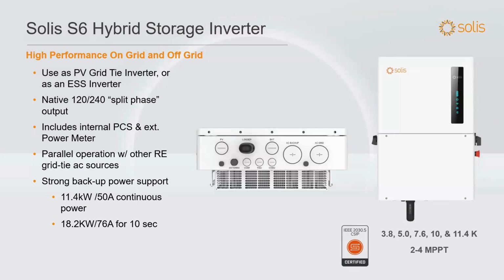That is, you'll find that all of the smaller grid tie inverters that I just showed you, and should you get into this 208 inverter or even into our larger commercial inverters, have a line 1, line 2, and a ground. Or in our three-phase, line 1, line 2, line 3, and a ground, no neutral. We derive a neutral with some math, and we don't really need it for our anti-islanding functionality. It's just a way for us to reduce your cost, reduce time, and make your conduit a little skinnier, because you don't need to run a neutral.